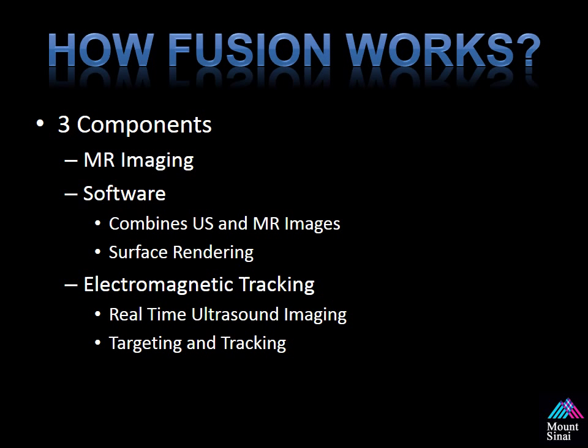Before we begin, it's important to understand how the technology works. Fusion technology uses three components. The first is the MR imaging. The second is the software used to combine the ultrasound and the MR images together, and this is accomplished through surface rendering, which I'll describe in a moment. The third component is the tracking mechanisms. In this platform I'll be discussing today, it uses electromagnetic tracking.